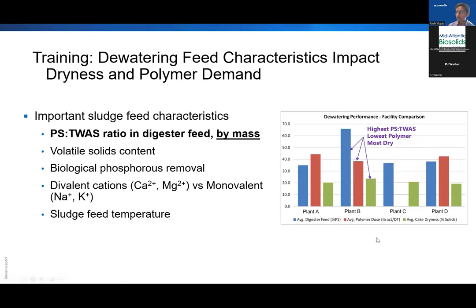And over here on the right, you can actually see a graph of the four facilities. And the one plant that had the highest primary sludge in its feed, which was the second plant, which was actually San Jacinto, you can see that it had the driest cake, which is the green column, and the lowest polymer dose of the utilities. And this utility was missing its data at the time, so it wasn't shown. But that just shows kind of graphically the importance of that primary sludge element and that overall ratio.